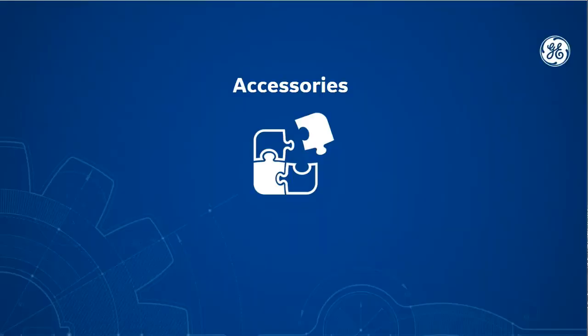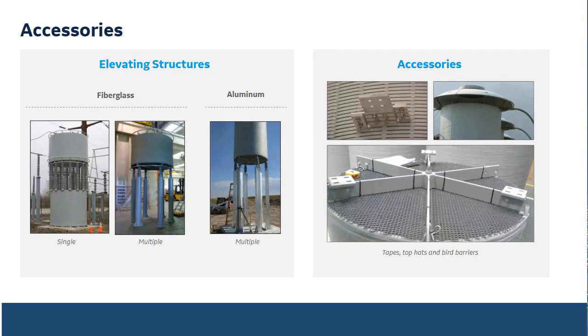Really quick here on the accessories that we are providing, which are typically provided with the reactors. Reactors are basically the round shaped cylinder big thing. They're provided with post insulators, which depend on the voltage level and BIL. They are also provided with elevating structures or pedestals. The pedestal depends on the magnetic clearance. It may also depend on electrical clearance or preference from the customer to have the reactors on ground or isolated away from ground. So if you have a specification for pedestal safety requirements, etc., just let us know. We will provide the pedestals or elevating structures based on your needs.